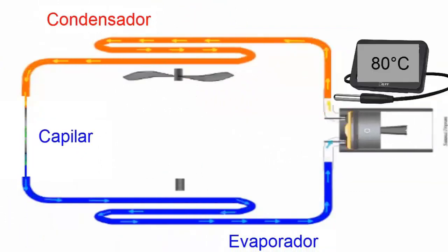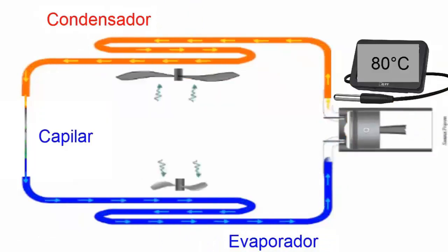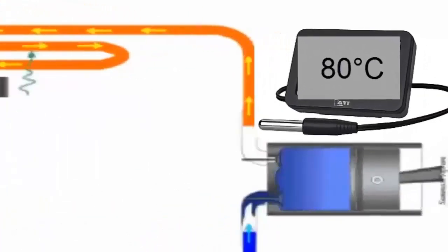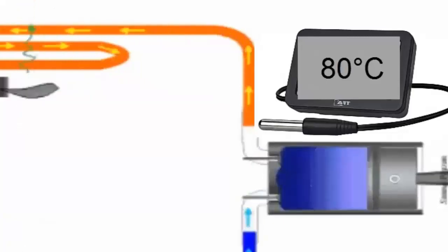Finally, we can say that equipment with refrigerant overload has temperatures immediately at the compressor outlet that are not far from normal values, generally below 100 degrees.